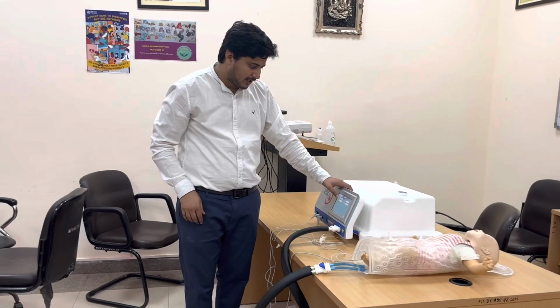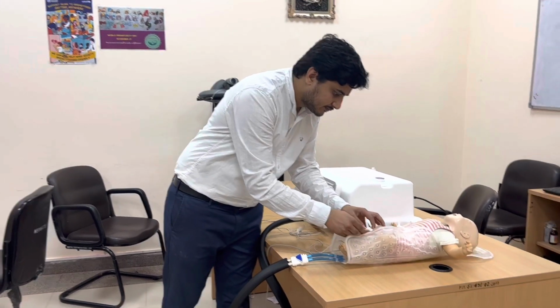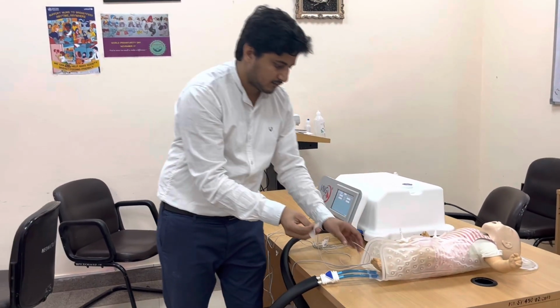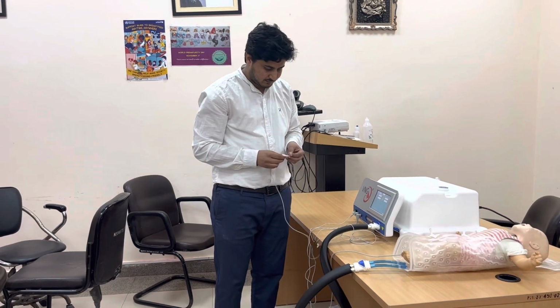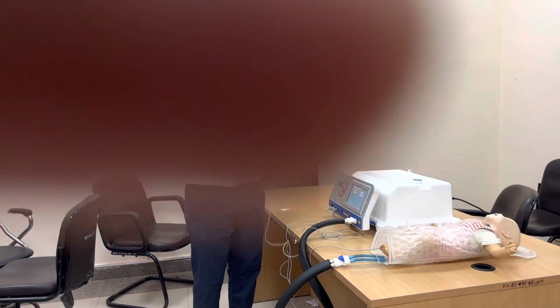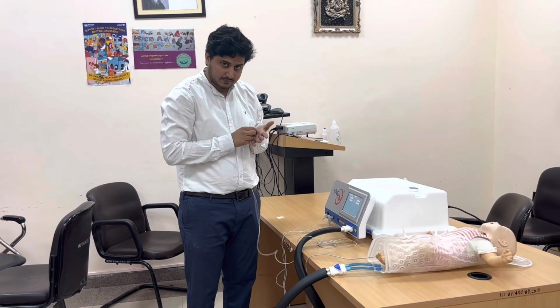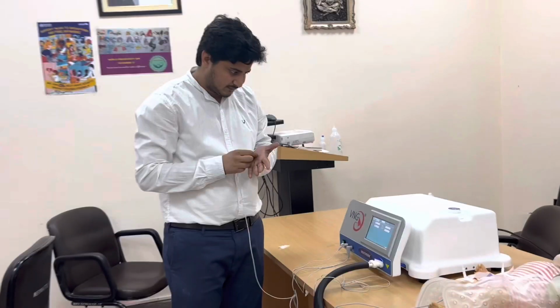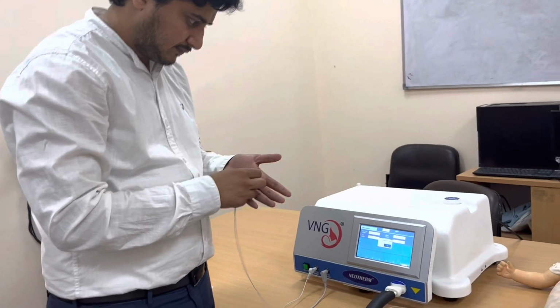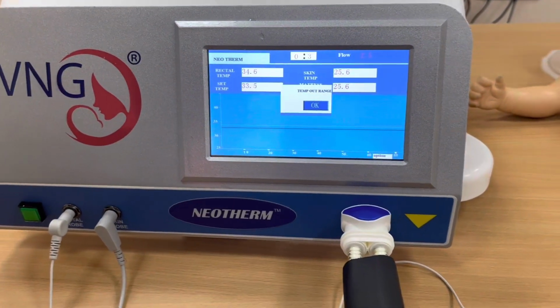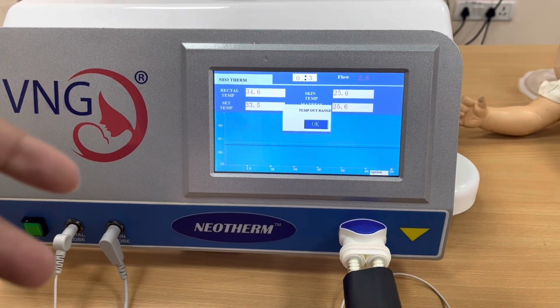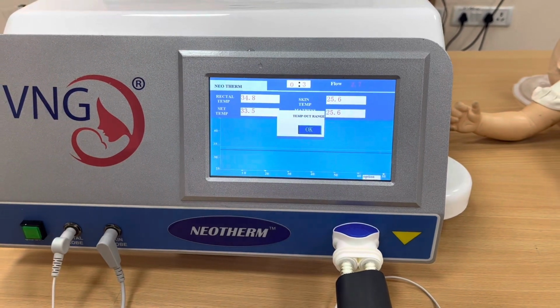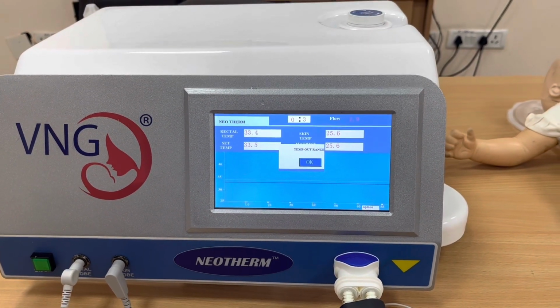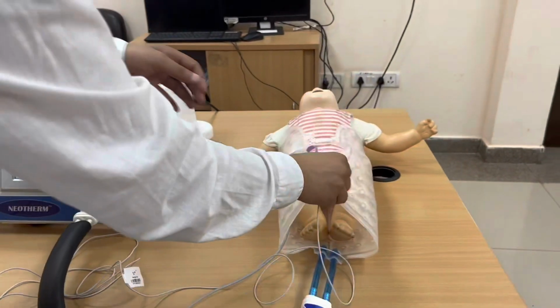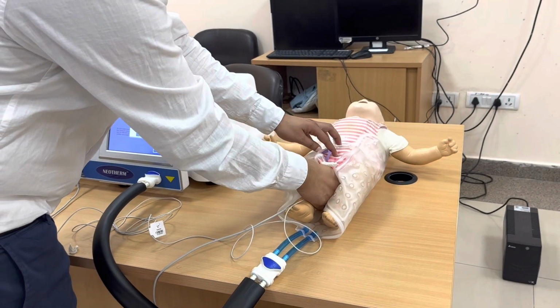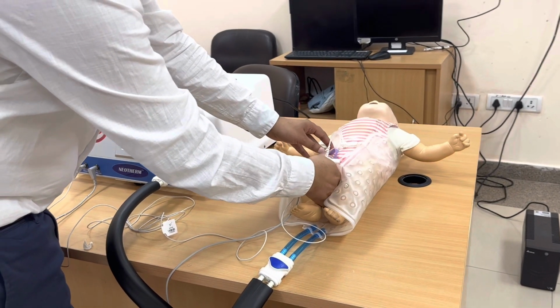Here I will try to demonstrate the alarm system of this device. Here you can see that once the rectal temperature has exceeded 34.5 degrees Celsius, the machine is giving an alarm. So whenever there is temperature deviation beyond the recommended set target core temperature range, the machine gives an alarm. Unless addressed, the alarm won't fade away.